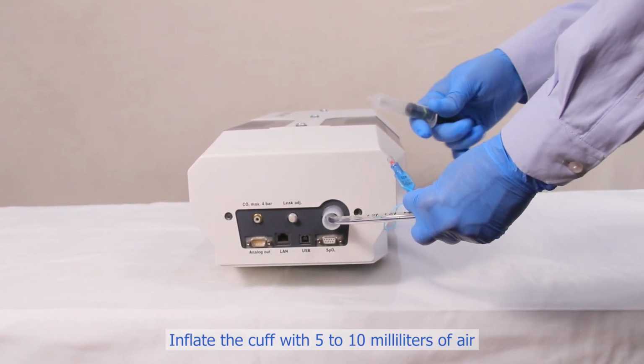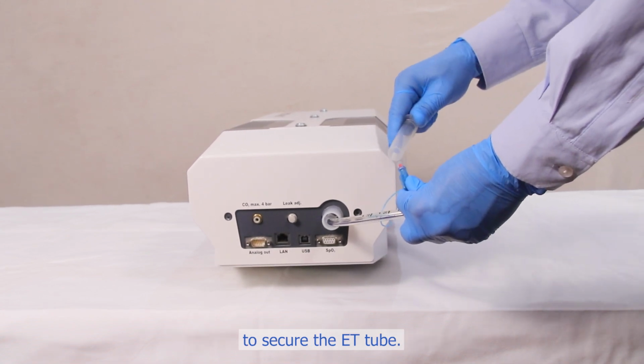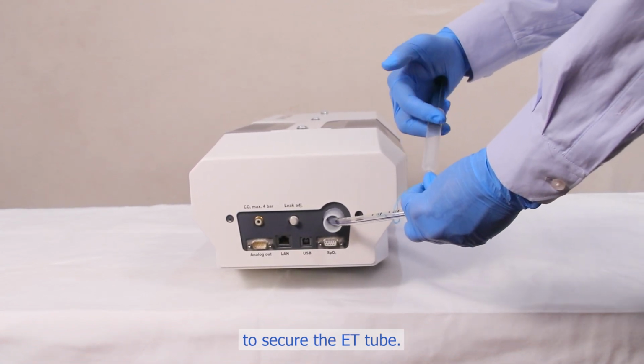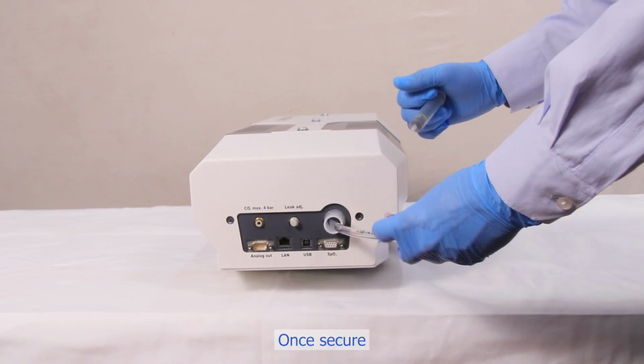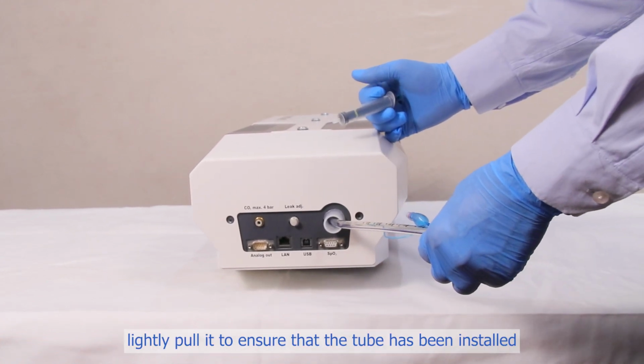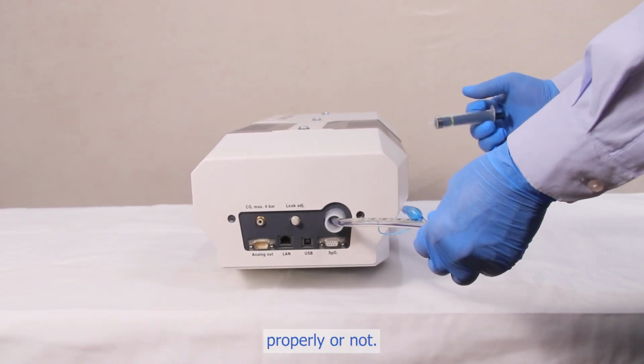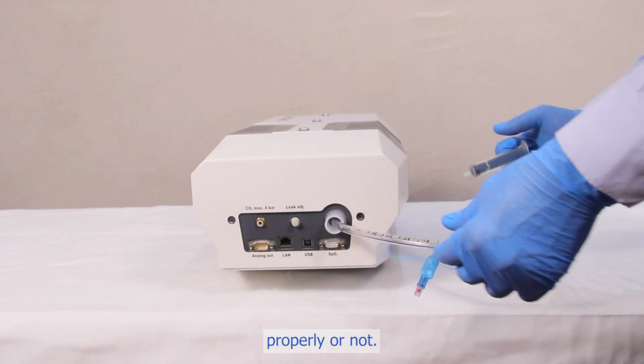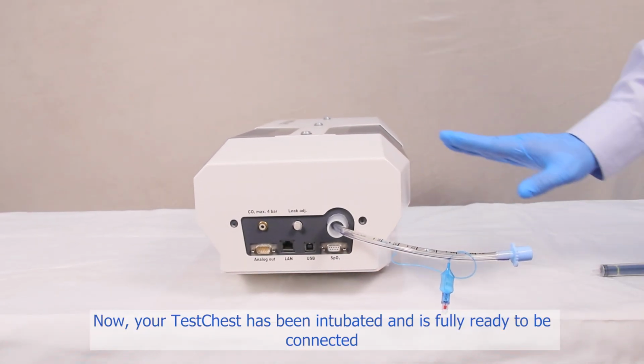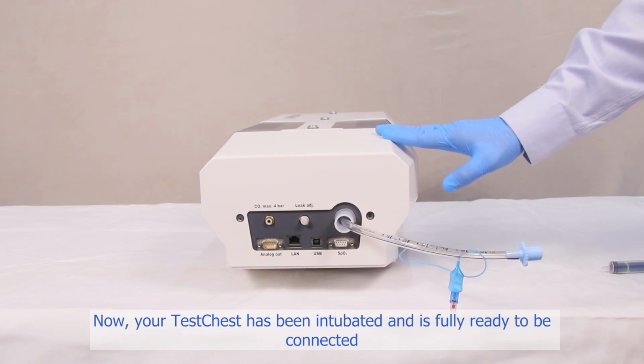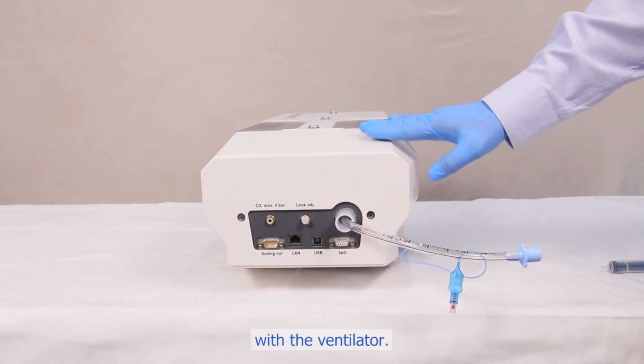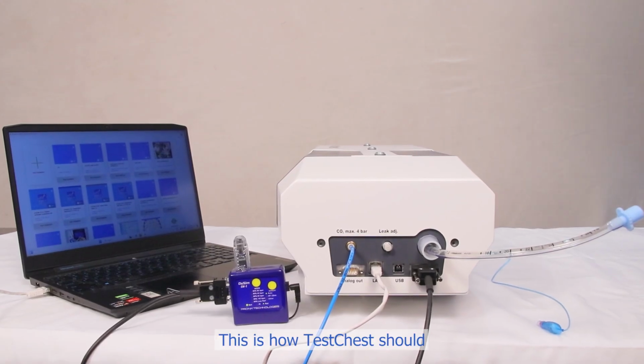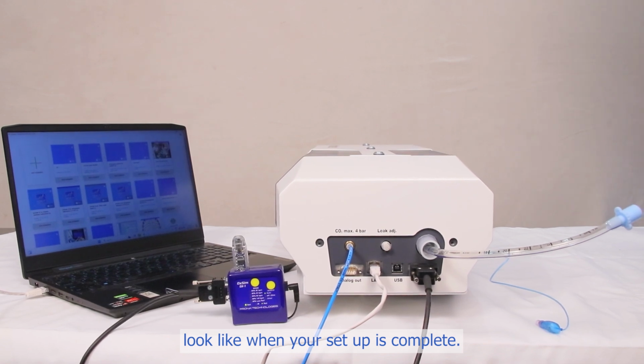Inflate the cuff with 5 to 10 milliliters of air to secure the ET tube. Once secure, lightly pull it to ensure that the ET tube has been installed properly or not. Now your TestChest has been intubated and is fully ready to be connected with the ventilator. This is how TestChest should look when your setup is complete.